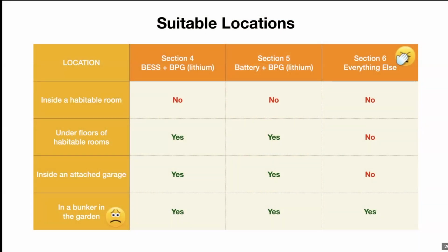It's a very narrow range of possibilities. Really, it has to be a lithium-ion battery because only the best practice guide applies to lithiums. It needs to be a pre-assembled solution that the manufacturer has deemed compliant to the best practice guide. You can't do any on-site manufacture of components. It must be basically a fully tested product that you're installing. So like I said, a Sonnen, an Alpha ESS, a Powerwall, a Varta, there's lots of them, is a pre-assembled BESS.